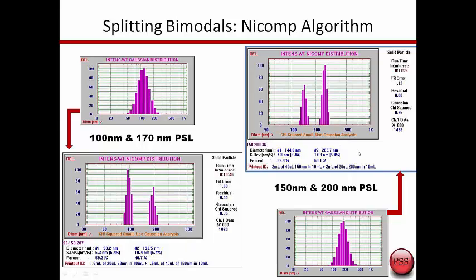The example on the right is showing similar results for samples that are at 150 and 200 nanometers. If we used a Gaussian distribution, it would merge it into a single peak. But when we applied the NICOMP algorithm, we split it into the two peaks at 150 and 200 nanometers. This kind of resolution is unique to the NICOMP and is one reason people prefer to use this when measuring complex samples.